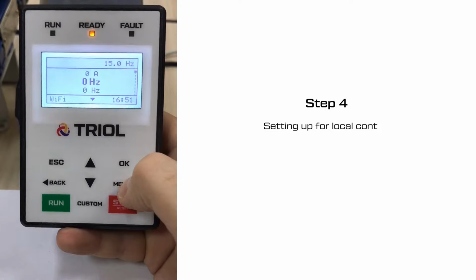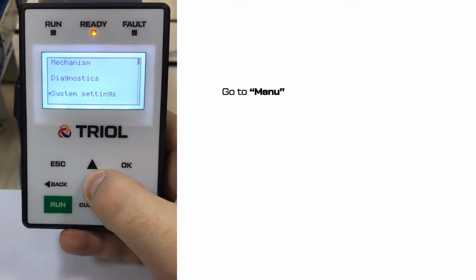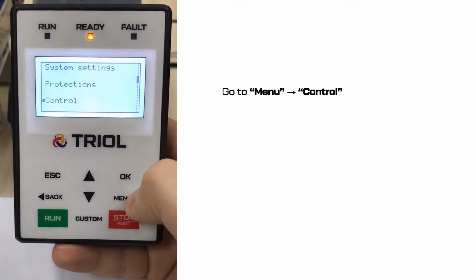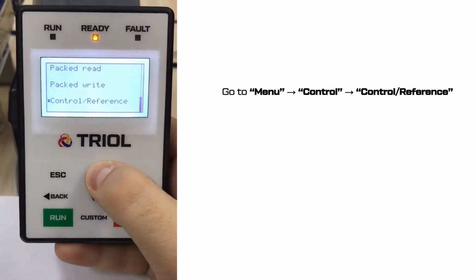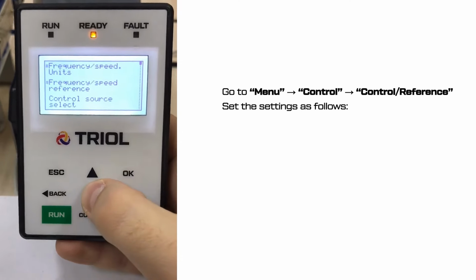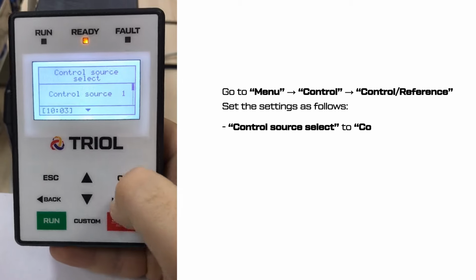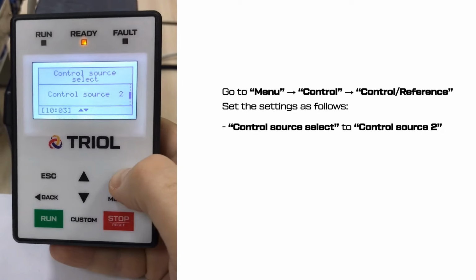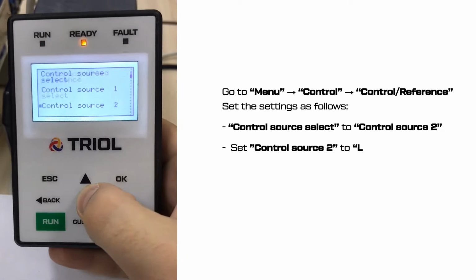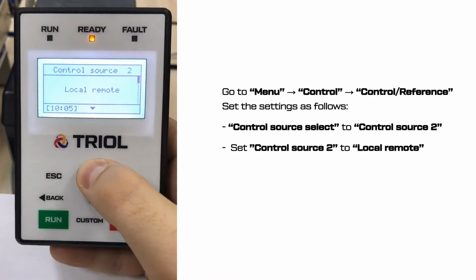Step 4. Setting up for local control. Go to Menu, then Control, then Control/Reference. Set the settings as follows. Control Source Select to Control Source 2. Set Control Source 2 to Local Remote.